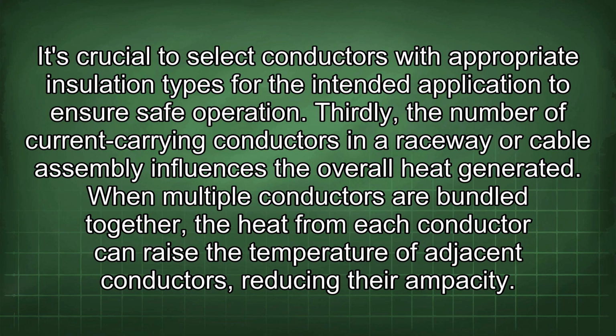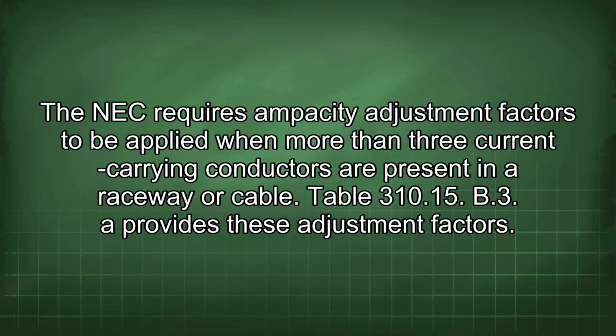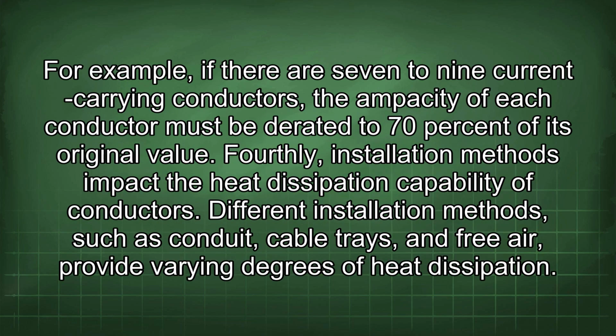Thirdly, the number of current carrying conductors in a raceway or cable assembly influences the overall heat generated. When multiple conductors are bundled together, the heat from each conductor can raise the temperature of adjacent conductors, reducing their ampacity. The NEC requires ampacity adjustment factors to be applied when more than 3 current carrying conductors are present in a raceway or cable. Table 310.15(B)(3) provides these adjustment factors. For example, if there are 7 to 9 current carrying conductors, the ampacity of each conductor must be derated to 70% of its original value.